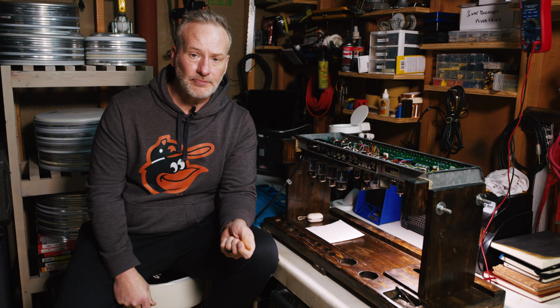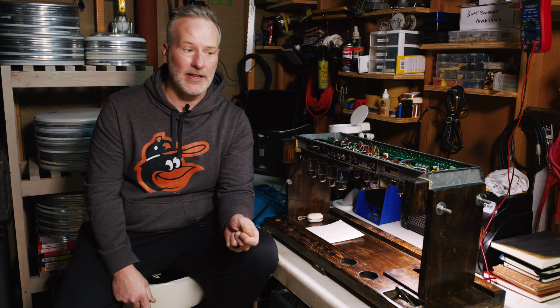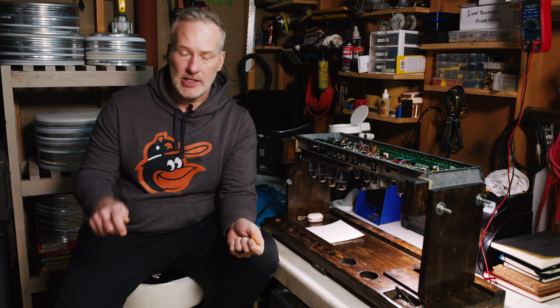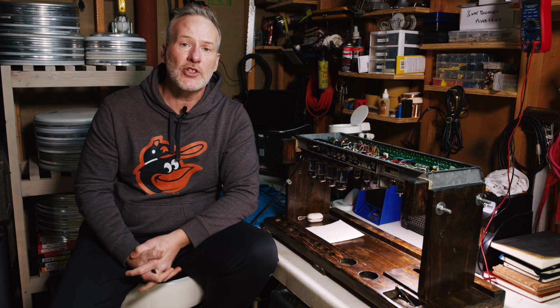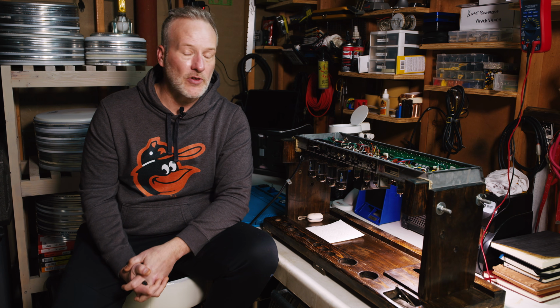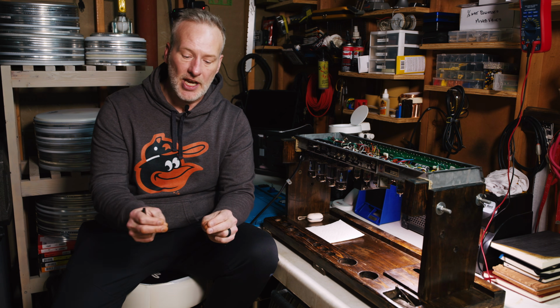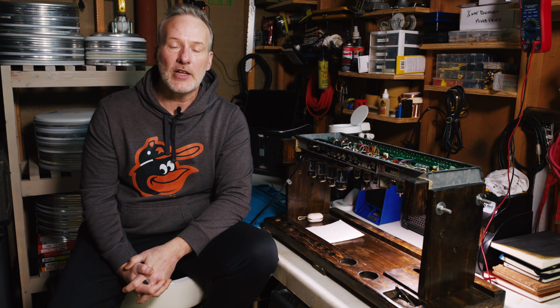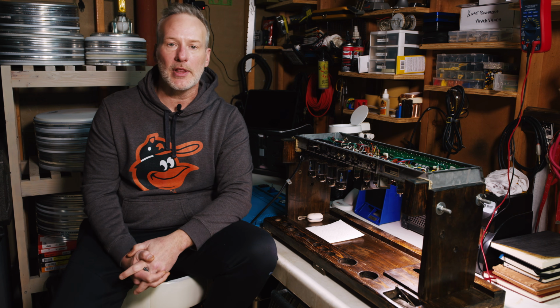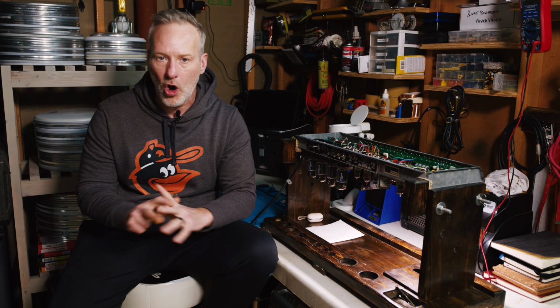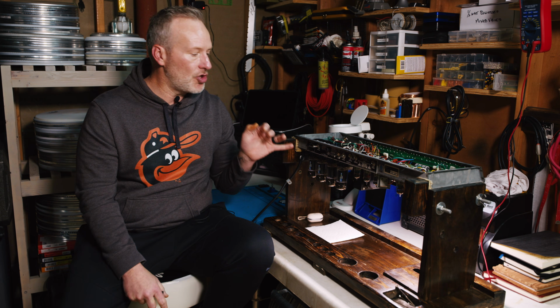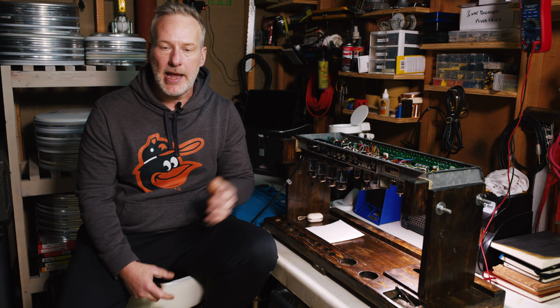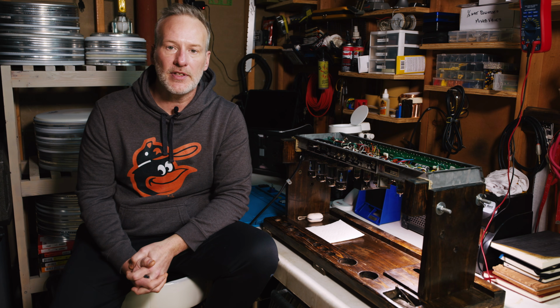Also know that if you hold the red lead against the positive capacitor leg, as long as that multimeter is grounded, it'll also start to drain the voltage out of it. But I like using that snuffer stick at the same time and checking the voltage as I'm doing it until I see that voltage drop to a level I know is safe. Check all the capacitors, make sure there's no power cords attached to the amp, and that amp will become safe to touch. And that's it.